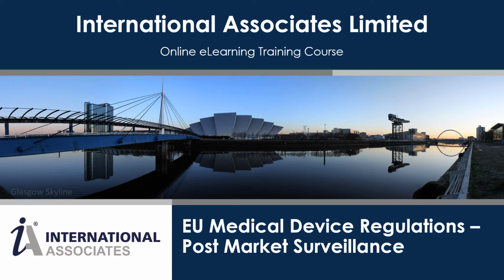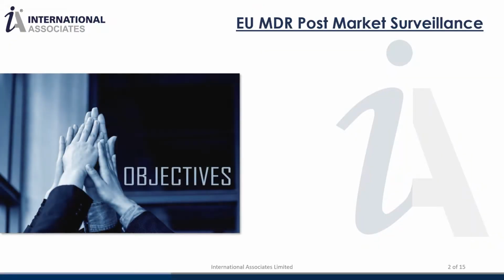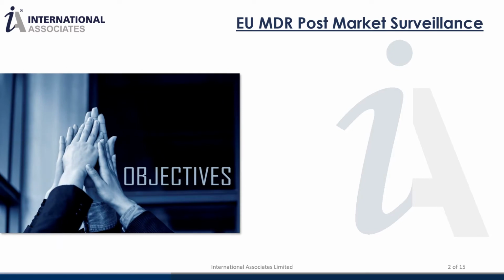Welcome to our guide on the EU MDR provision for post-market surveillance. For each medical device that is to be sold on the European Union market, the manufacturer must prepare technical documentation to demonstrate that the device was designed and manufactured according to all applicable medical device regulation (MDR) requirements. This includes information relating to post-market surveillance.